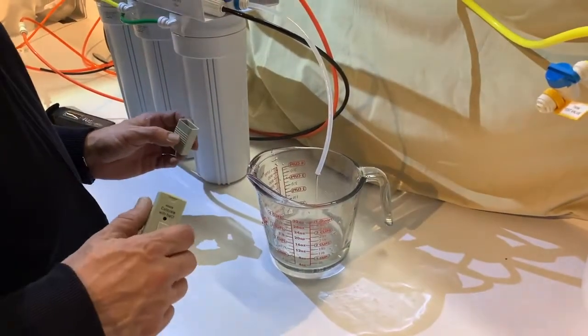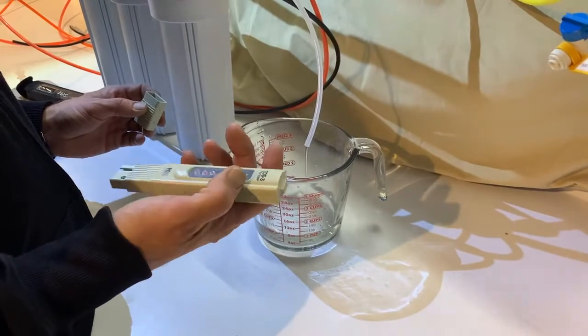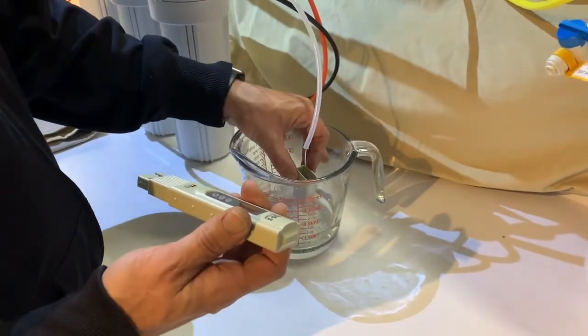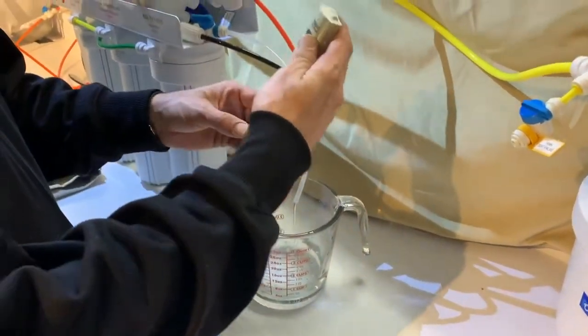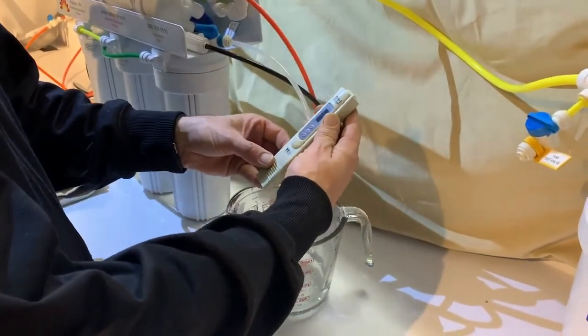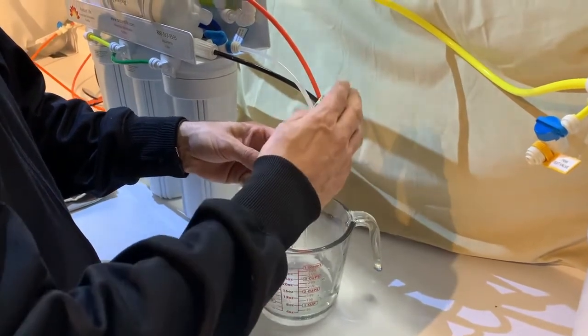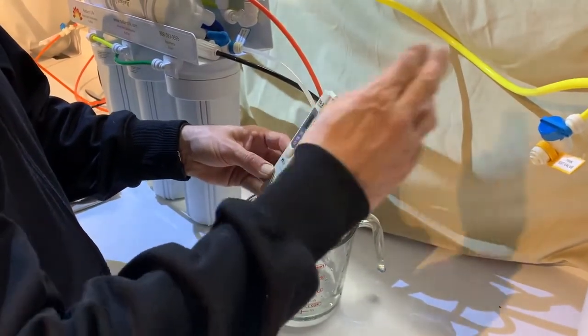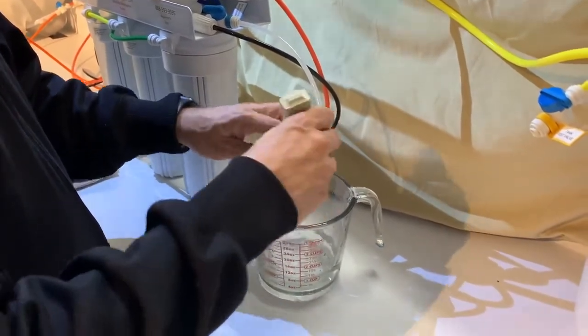Now that this valve's flushed for 90 seconds, you can still see that there's a slow trickle coming out with the meter on. Again, you're going to fill this cap a third to a half full. Just continue to let that valve run. It'll be fine. Put that in there, get your reading. In this case, it is most likely going to be higher than your tank test valve. Repeat these readings five times and record all five.